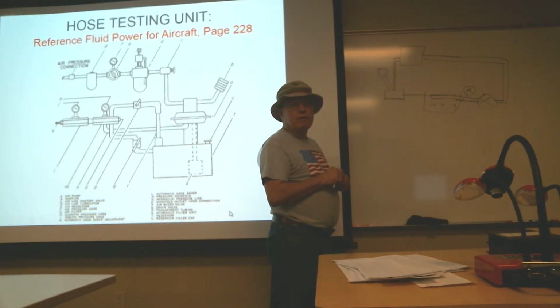Anybody know? Is it 1 minute? Not a minute. 30 seconds? Usually 1.5 times system pressure for a minimum of 30 seconds.